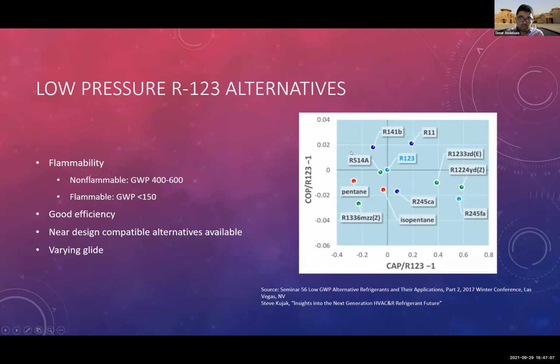So for R123 alternatives, we can see that there are some non-flammable refrigerants with GWP ranging between 400 and 600. This is a higher GWP than R123, so it's not necessarily a good option. There are some flammable options with GWP less than 150. Most of the alternatives are with good efficiency, and there are some near design compatible alternatives. However, the glide might vary quite a bit.